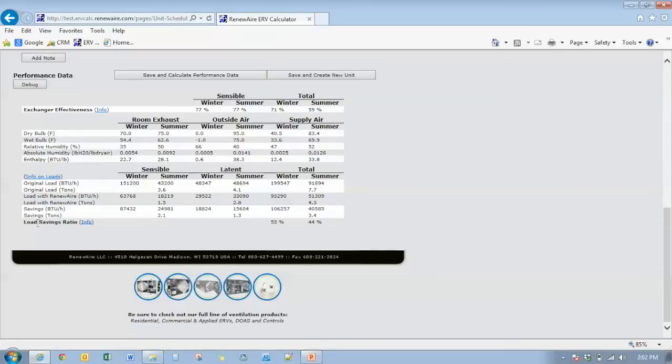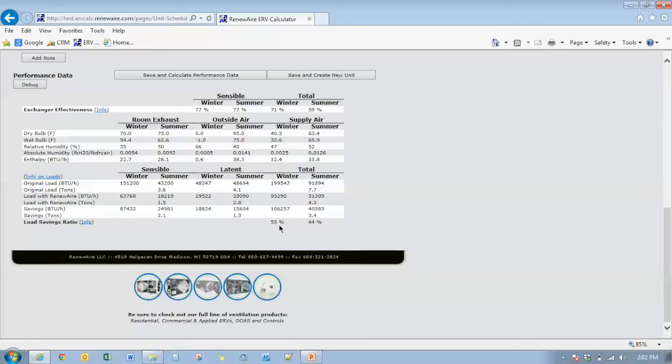And the load savings ratio, the energy recovery, the load reduction of the outside air coming in has gone down slightly because you have more outside air being introduced than you have exhaust air going out. So that's where you'll see the difference in those effectiveness numbers. We can unbalance those in the opposite direction.